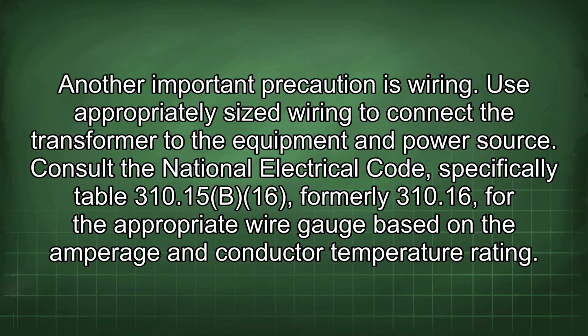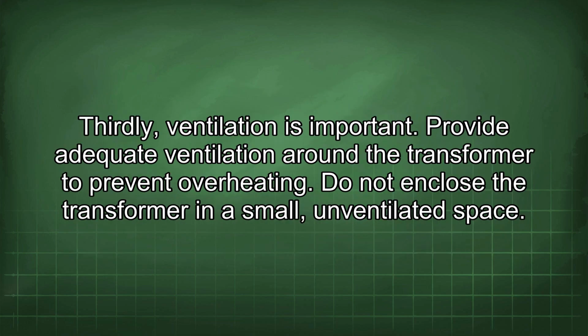Use appropriately sized wiring to connect the transformer to the equipment and power source. Consult the National Electrical Code, specifically Table 310.15(B)(16), formerly 310.16, for the appropriate wire gauge based on the amperage and conductor temperature rating. Thirdly, ventilation is important. Provide adequate ventilation around the transformer to prevent overheating. Do not enclose the transformer in a small, unventilated space.